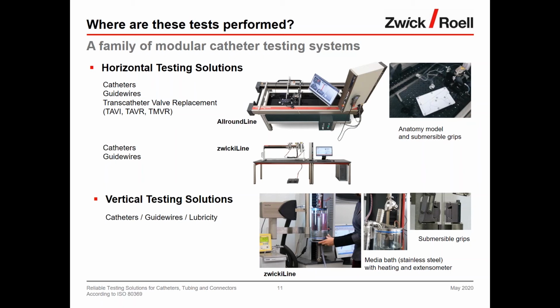Okay, I got it. Is there any difference in testing between R&D, for example, and production or quality assurance? And if so, can you tell us a little bit more about that? Yeah, definitely. So in R&D and design verification, they are much closer to real-life requirements. That means they do simulations of the intervention that are performed by the doctor in a, let's say, close to investigation setting. This can be implemented very well with our modular horizontal testing machines, either in a dry setup or with human body conditions with submersible components in a media bath, heating and circulatory pump systems. In production, in contrast to that, the tests are much simpler and are mainly tensile and/or compression tests.